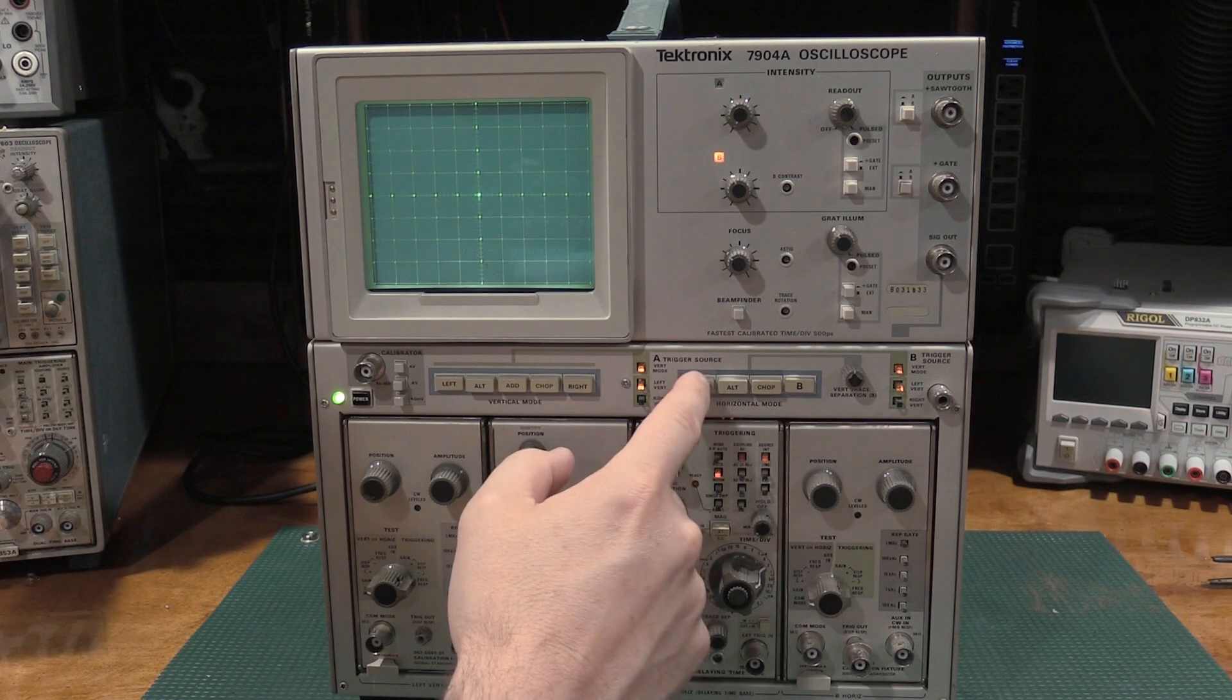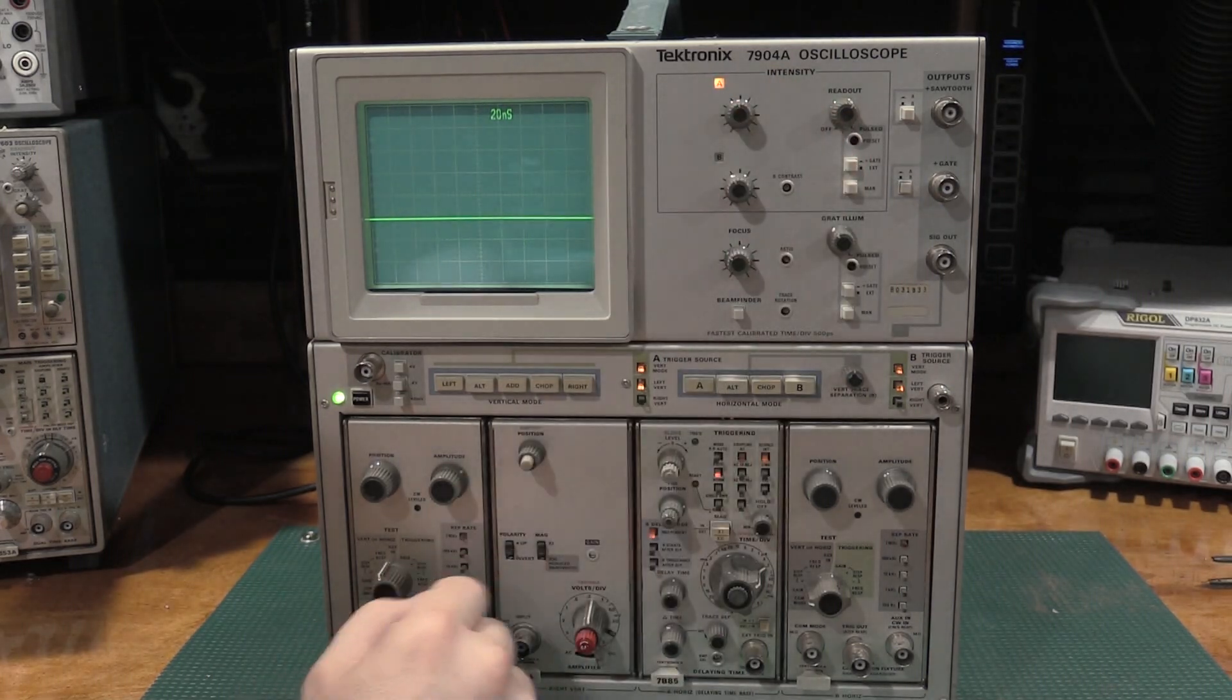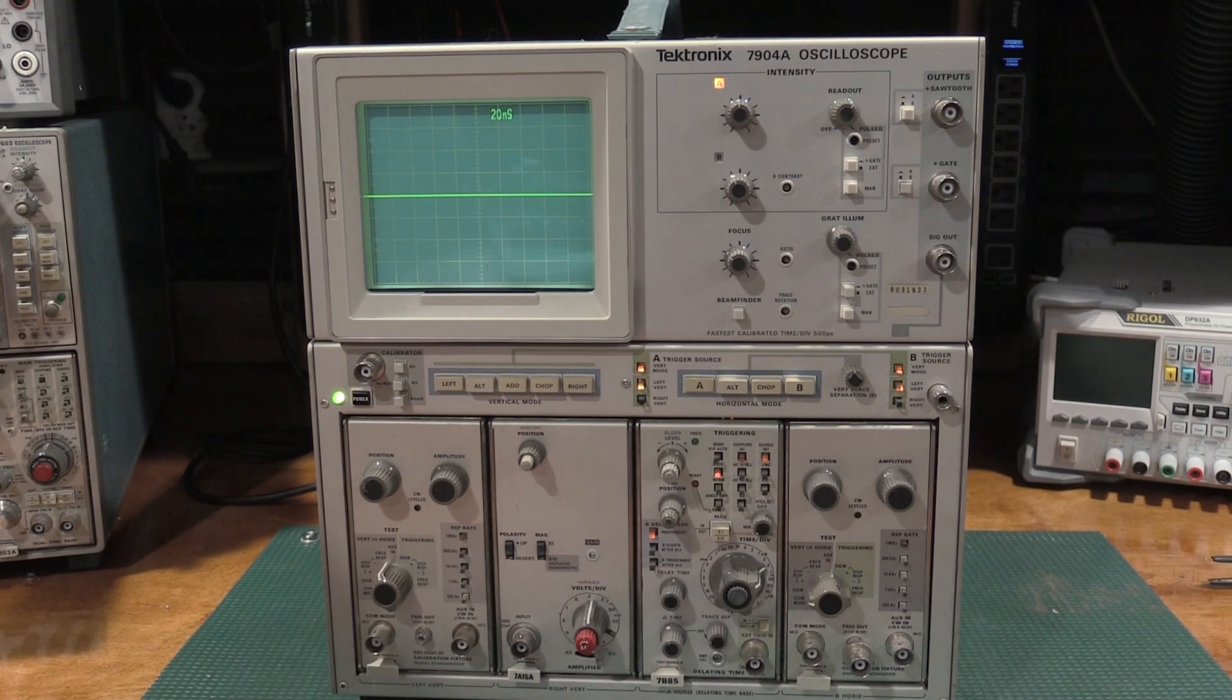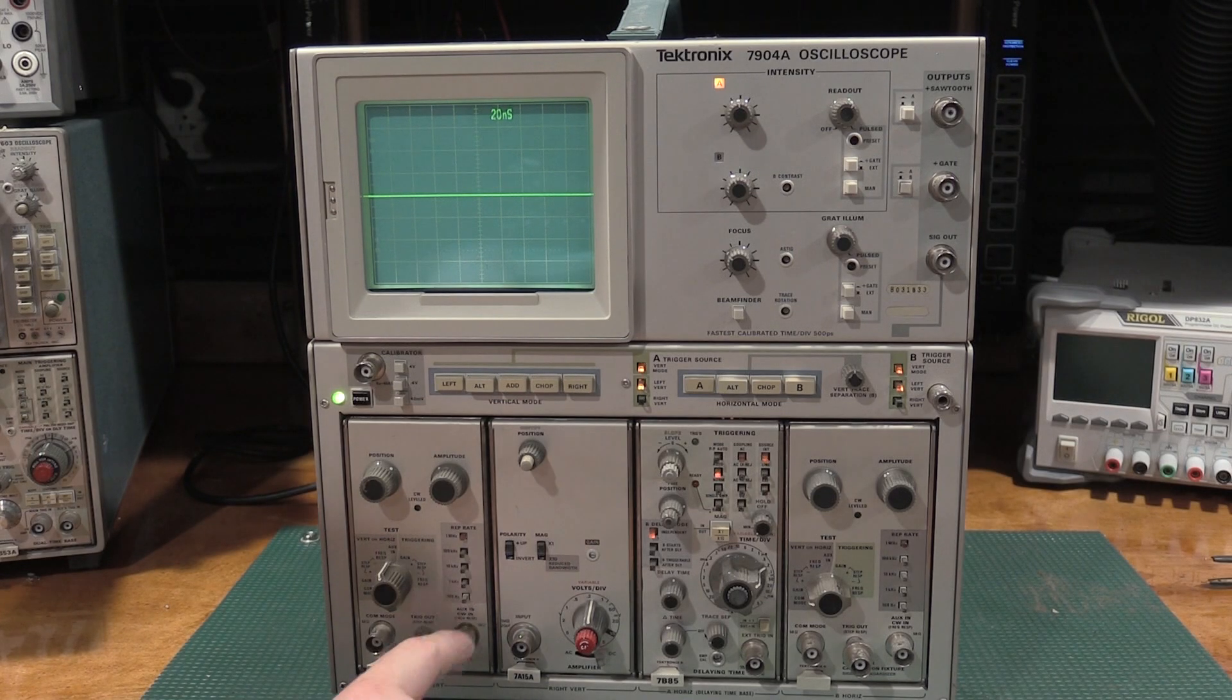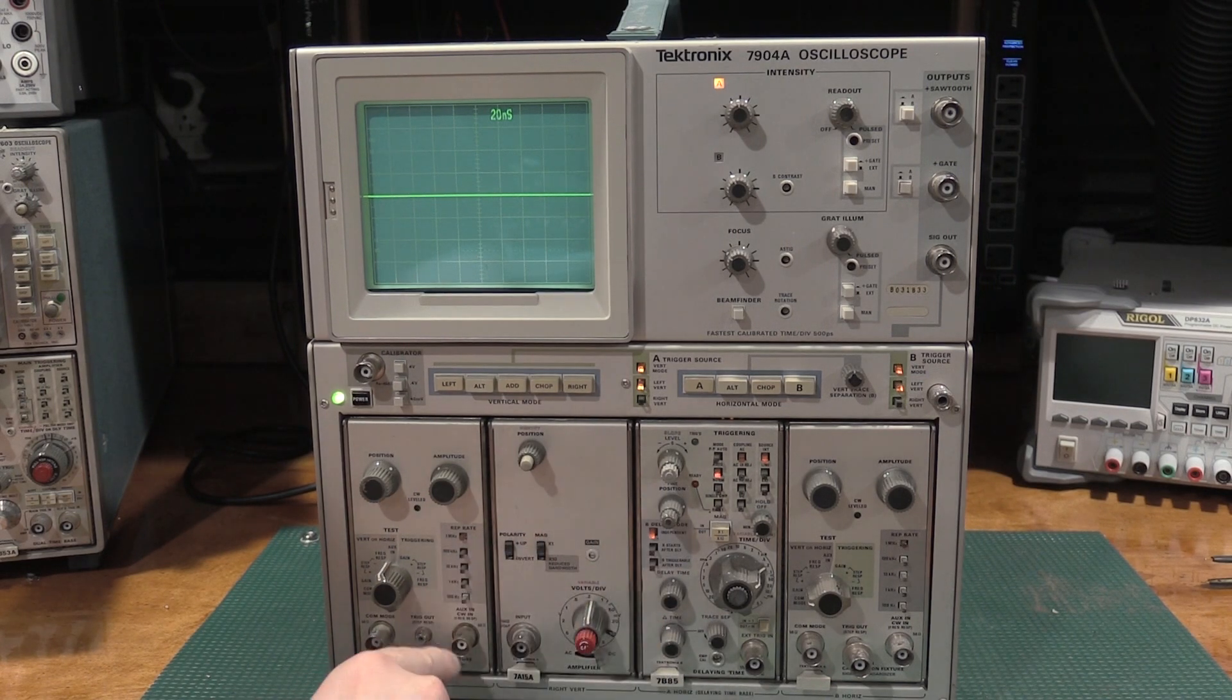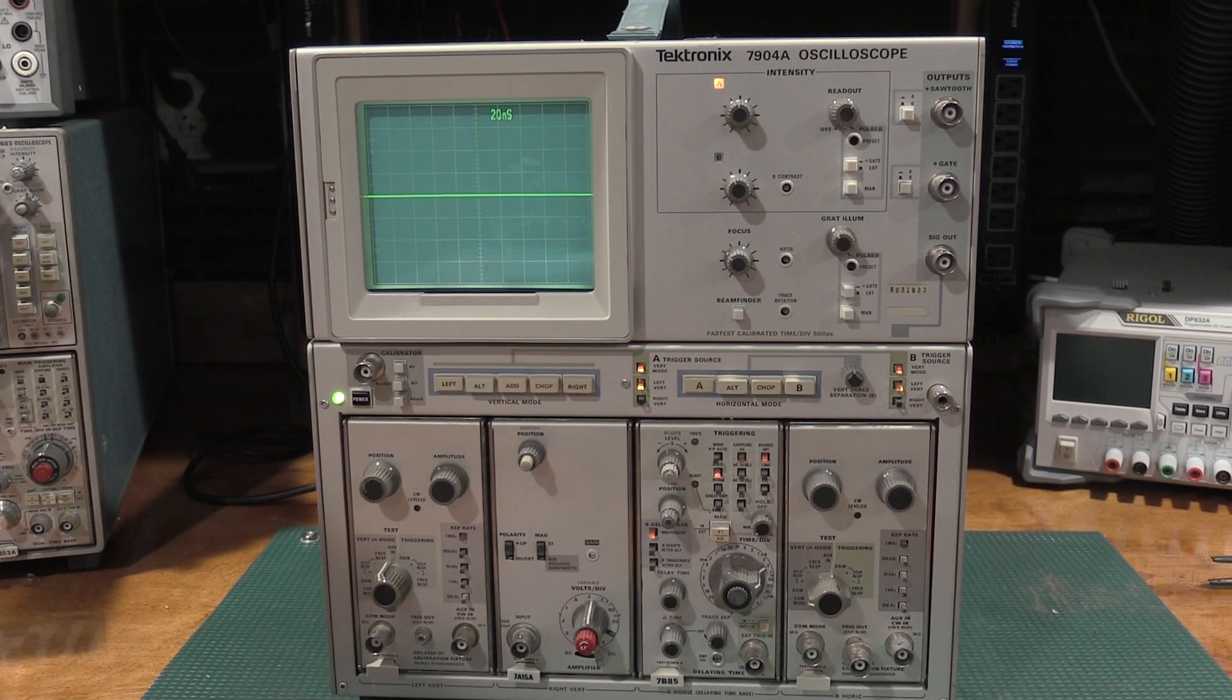Let's go back to A. Let's see what frequency response might give us an interesting waveform. No, because that probably needs an external signal. Yeah, nothing's triggering, so it may need, yeah, carrier, carrier in for frequency response, so it needs a SG503 signal or something in here where you can do, and then you also have some amplitude adjustment on the frequency response, too, so you can level the SG503, adjust this for whatever settings, the calibration document's calling for, alignment document, and go from there.